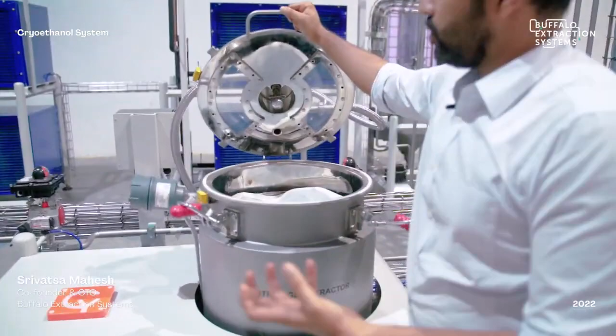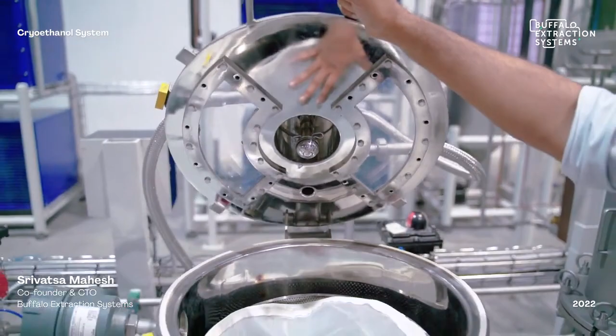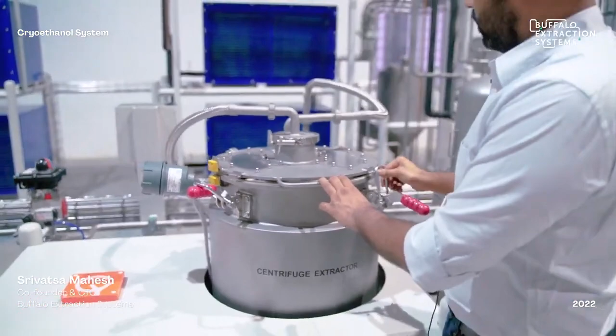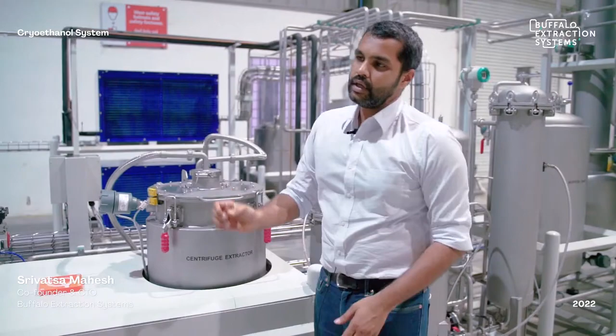And if you see here, you have a spray ball which injects the ethanol, which is at a cryogenic temperature, into the vessel. There are limit switches and safety switches and level sensors that ensure that there is neither an overfilling of ethanol, nor is this centrifuge used when the lid is not closed properly. So you ensure a very safe operation throughout the process.